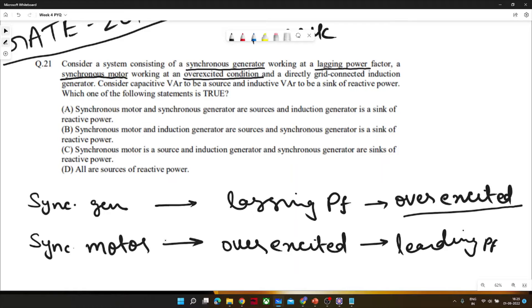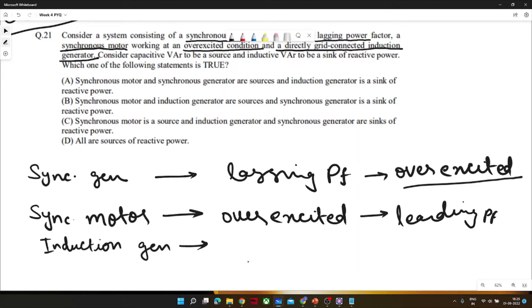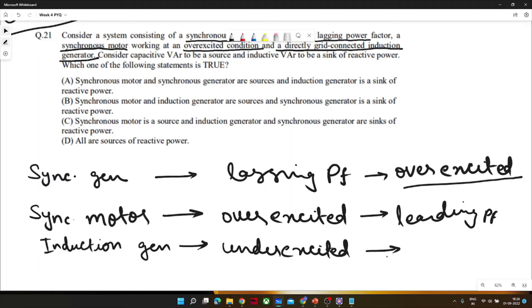Now, a directly grid-connected induction generator is also in the system — so three machines are tested at once. An induction generator cannot be over-excited because it consumes a lot of reactive power, so it would always be under-excited. It can give other machines real power or active power, but it cannot supply reactive power — that is the drawback of the induction generator.